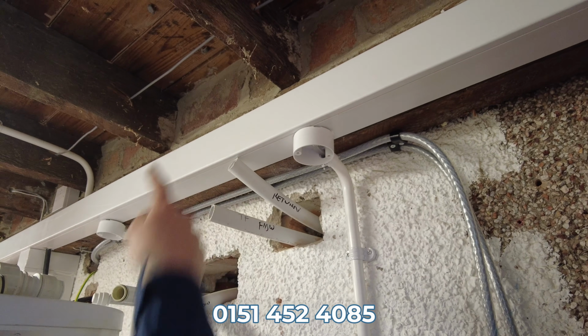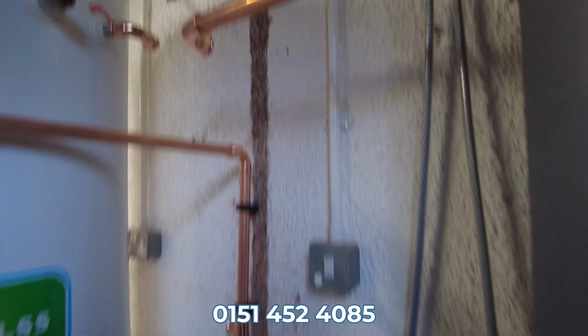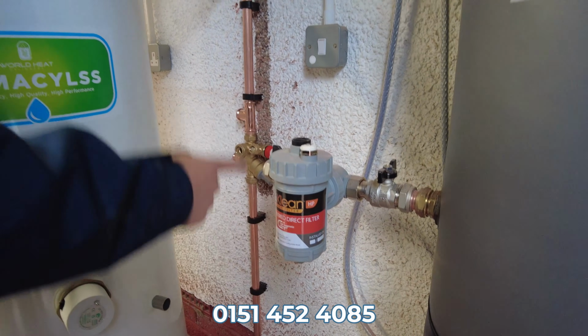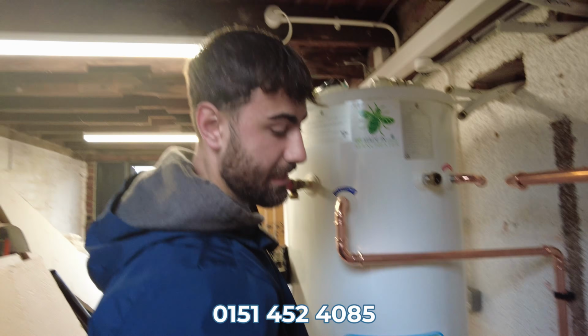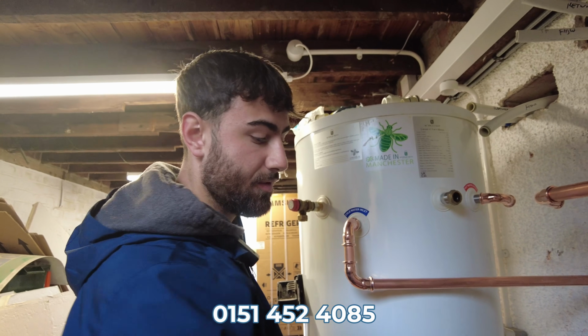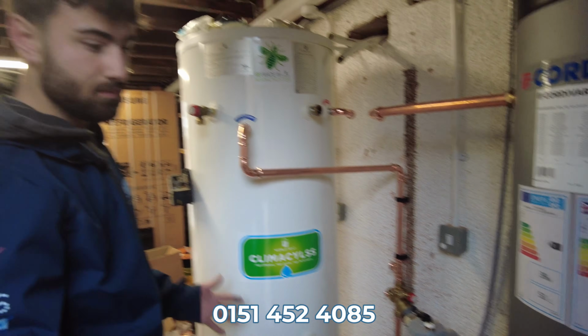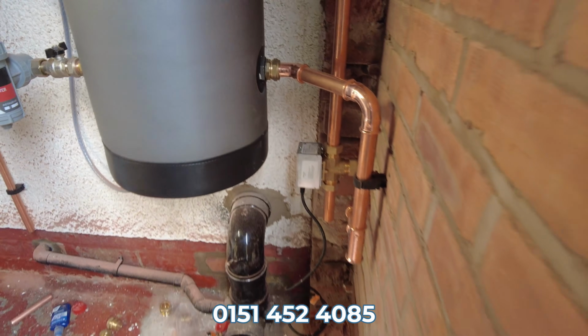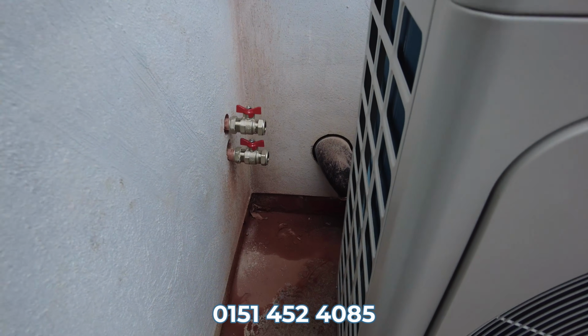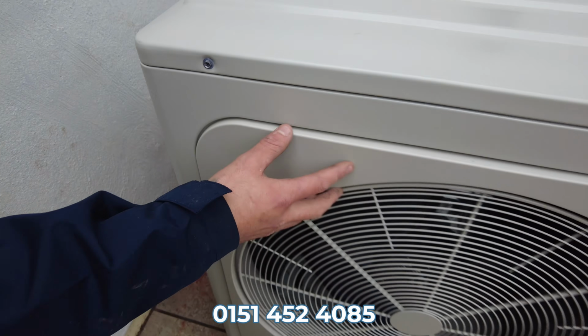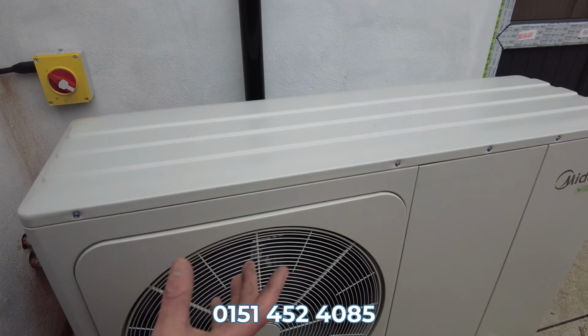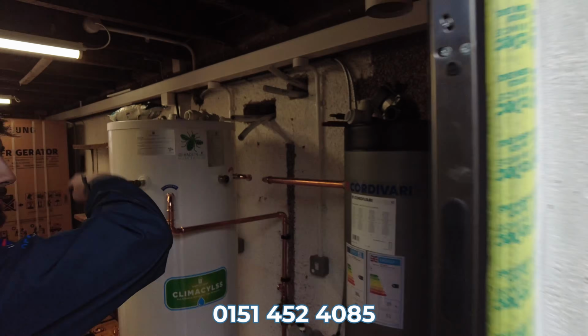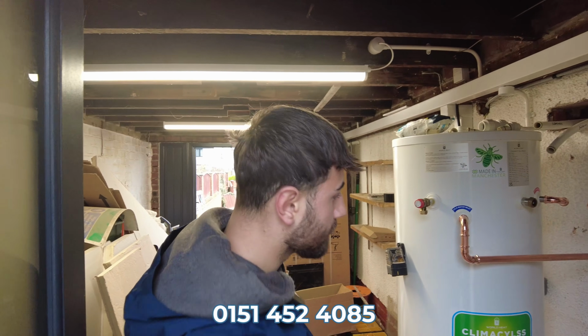Then it comes back through this pipe down into here, into a filter. So this filter takes all iron, anything that's constantly circulating through. It helps your heat pump not get clogged up with stuff and helps protect it. So then that comes back out here, down, through there and back. It'll eventually come out of there into the back of the heat pump, circulate again, heat up, come back through, and then it just keeps in a big loop going round and round.